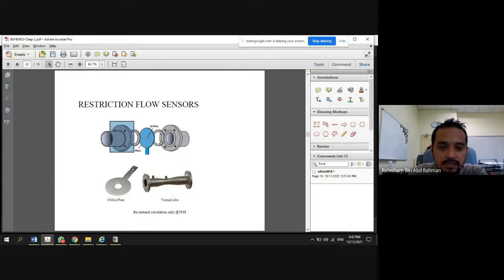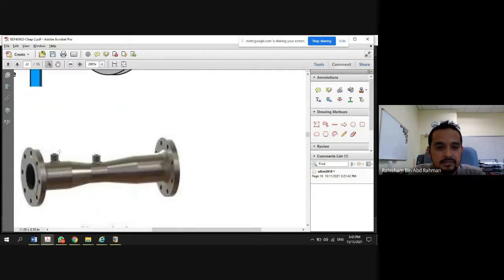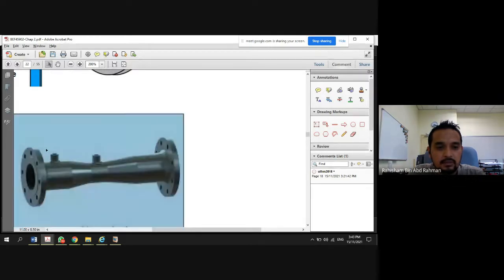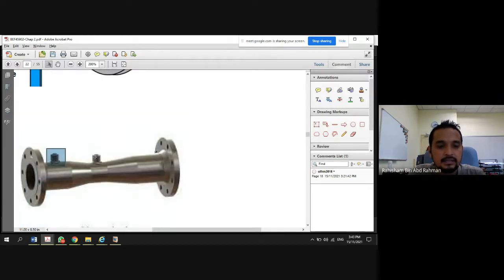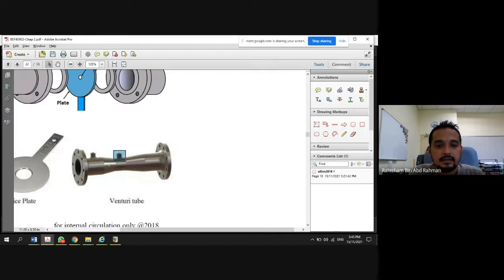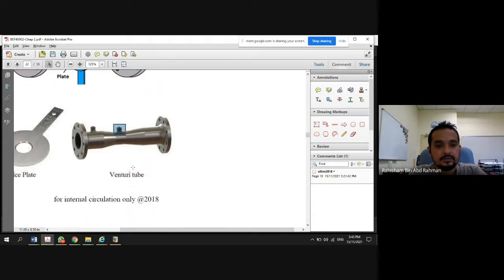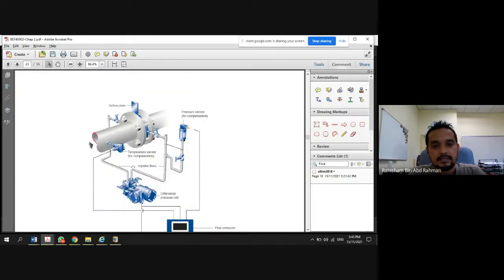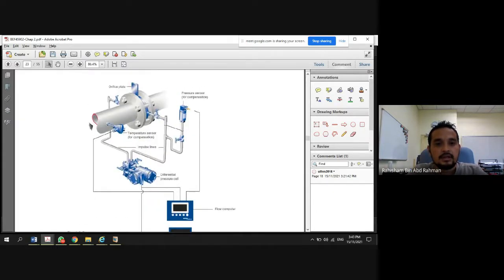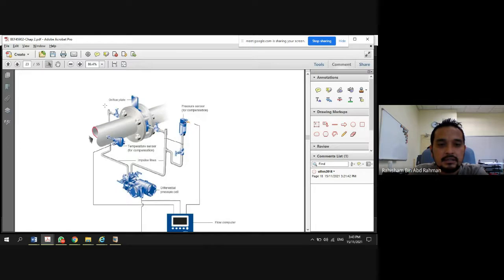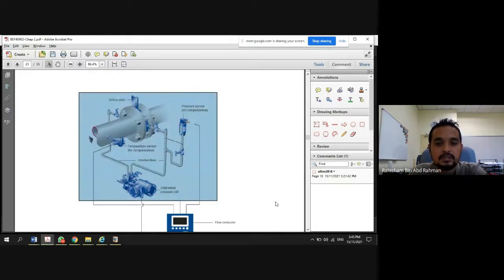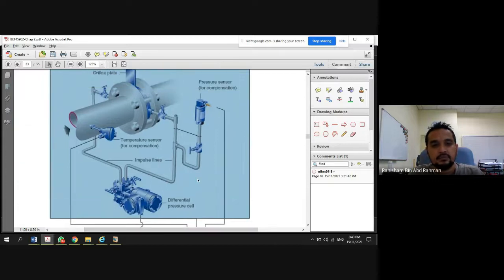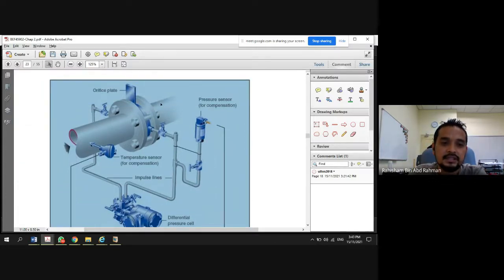All right, this is the orifice plate, as you can see, and this is the venturi tube. If you can see here, this is the one we use to measure pressure 1. This is pressure 2. This is the one we use in the pipeline. Then this will be connected to the DP transmitter, so that we can measure the pressure difference. This is a very typical illustration if you go to the oil and gas industry, in which you will constantly see this arrangement.